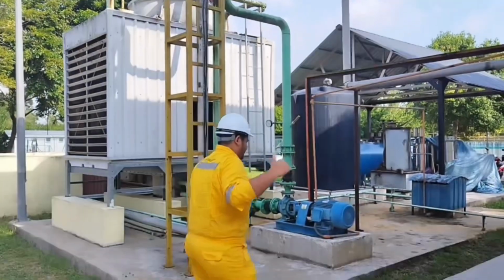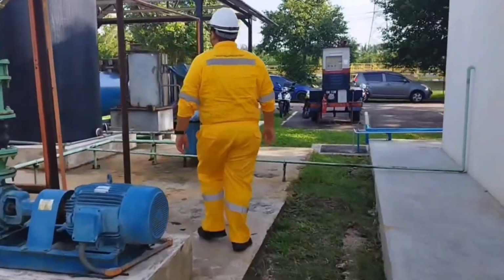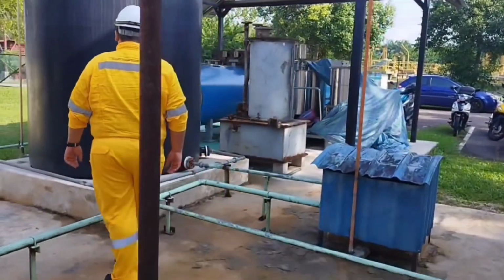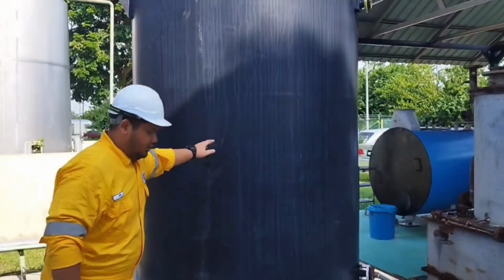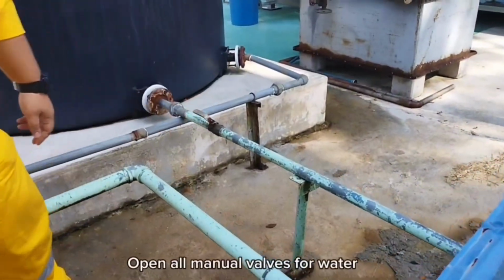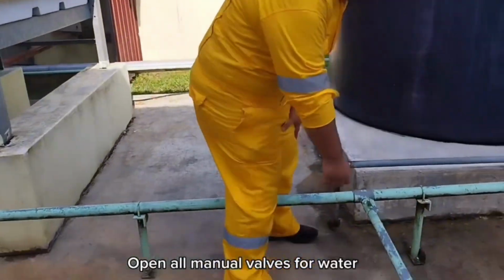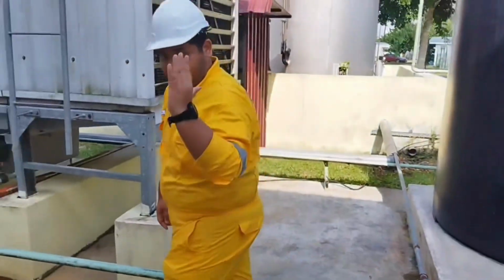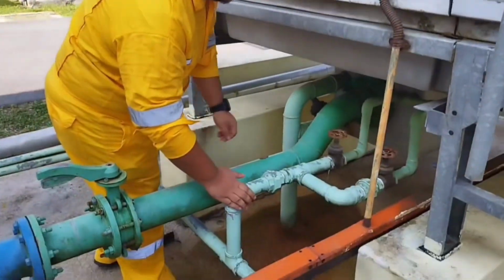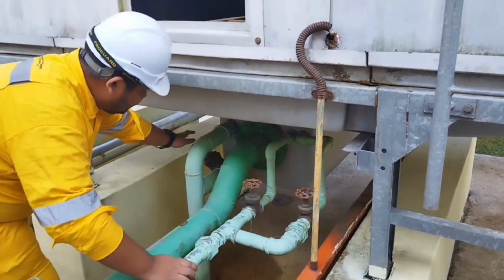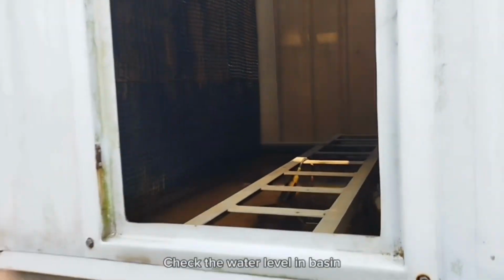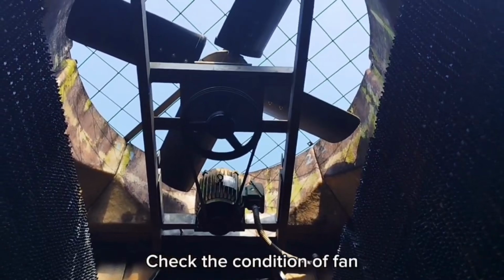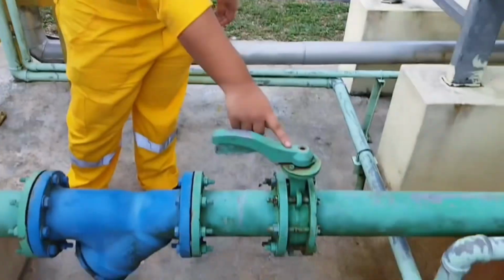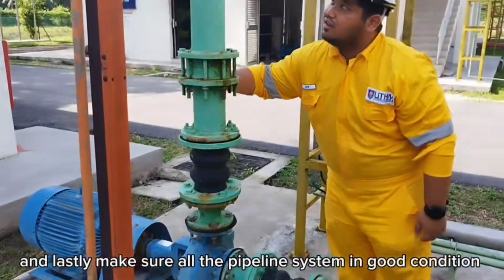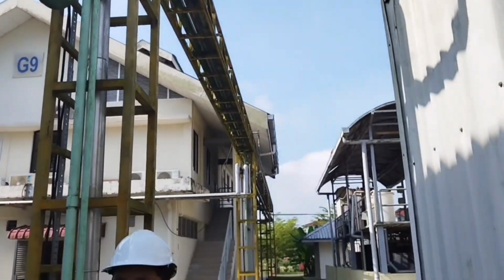So the first step is the pre-startup process, where we manually open and check all the equipment. It is also to ensure the equipment is in good condition for running. The first step is to check the water level in the water tank and also to open all the manual valves for water. We have to make sure all the valves for the cooling tower are open. And next we also have to check the valve that supplies the water from the water tank to the basin, and then we have to check the water in the basin itself to make sure it is in good condition. We also need to check that the fan is in good condition, and lastly we have to check the pipeline system, make sure all is in good condition, and then we are settled with our pre-startup process, so we are ready to start.